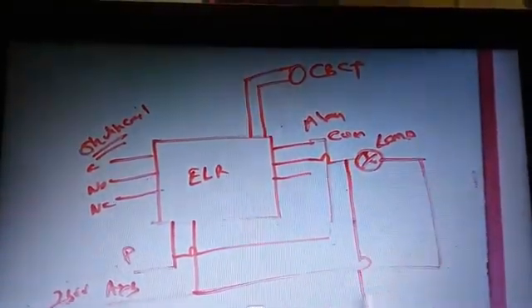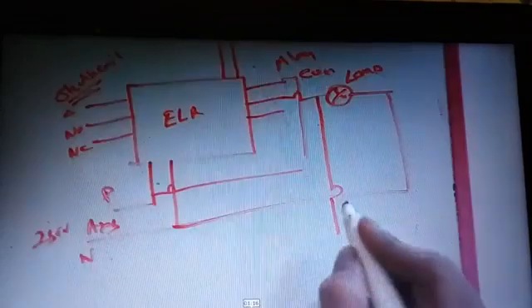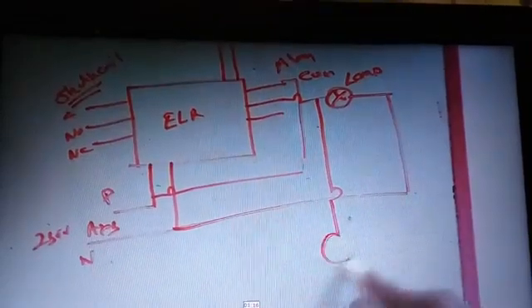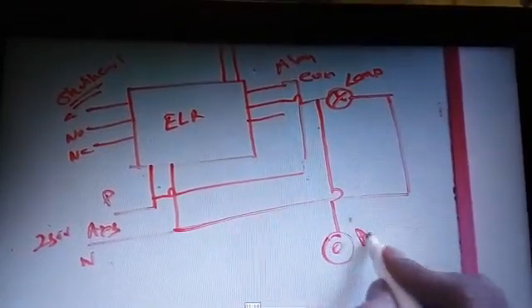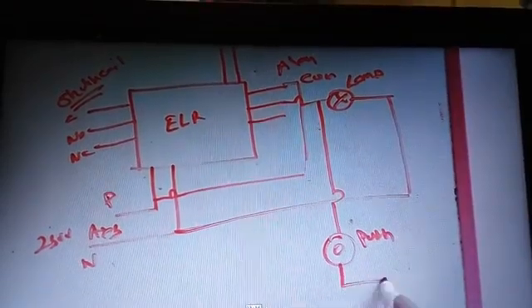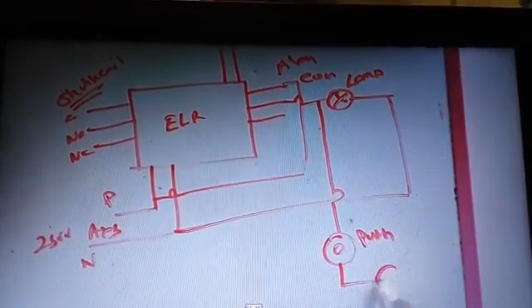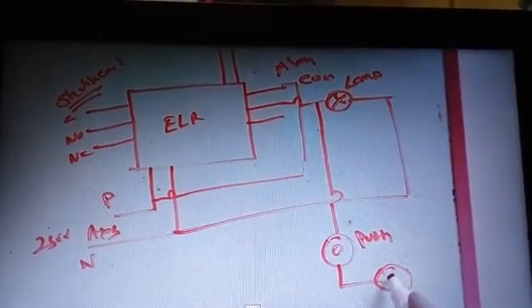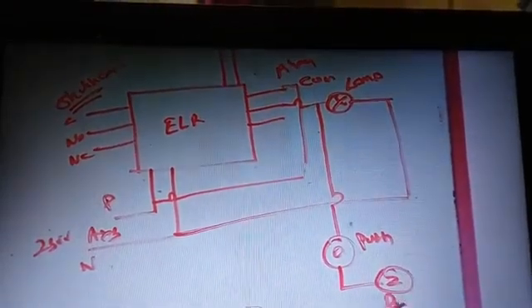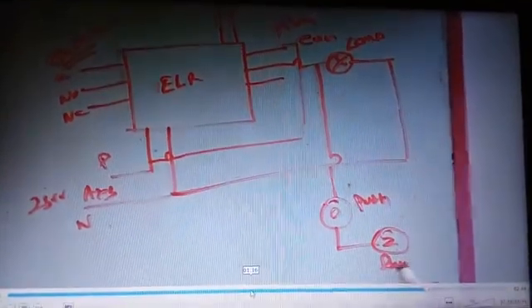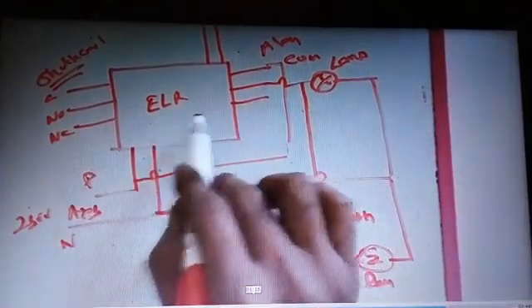We are giving phase supply for the indication lamp and taking output from the normally-open contact for the indication lamp. Another one is looped for the push button. After the push button we are giving to the buzzer, and we are looped to neutral also. This is the general connection of the ELR.